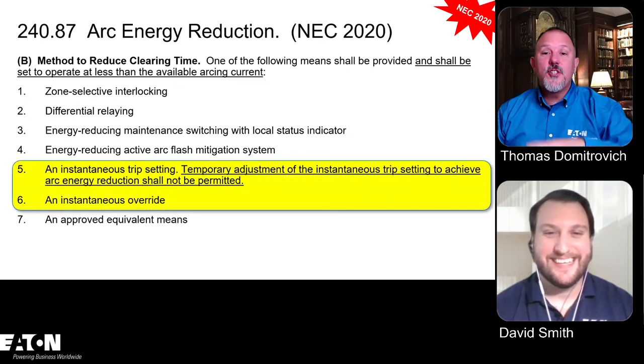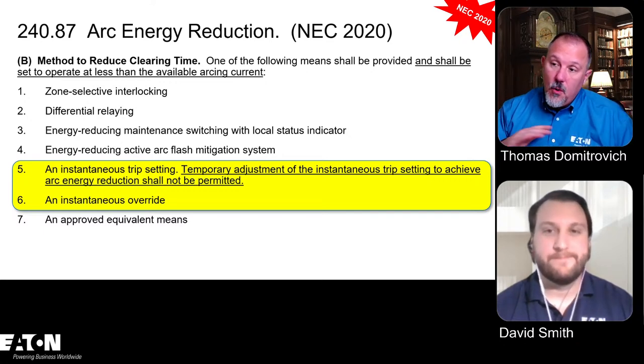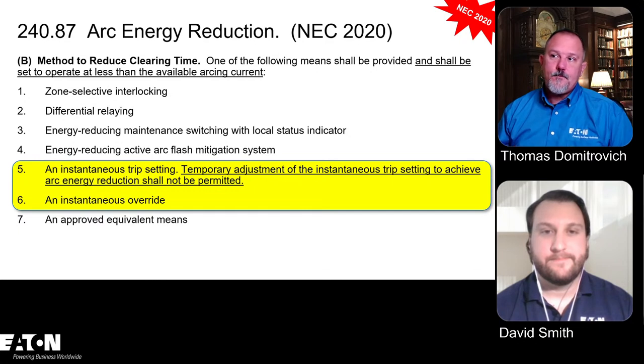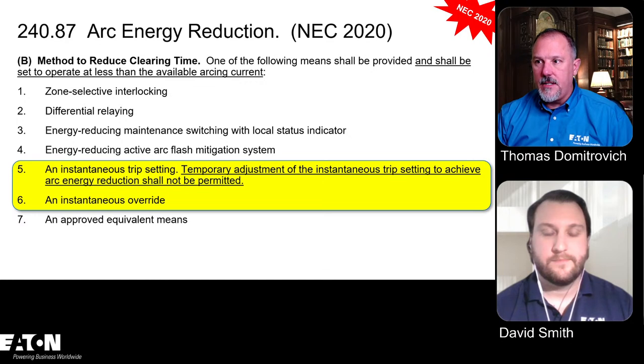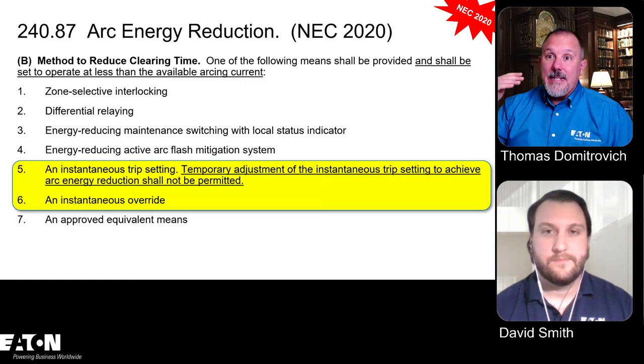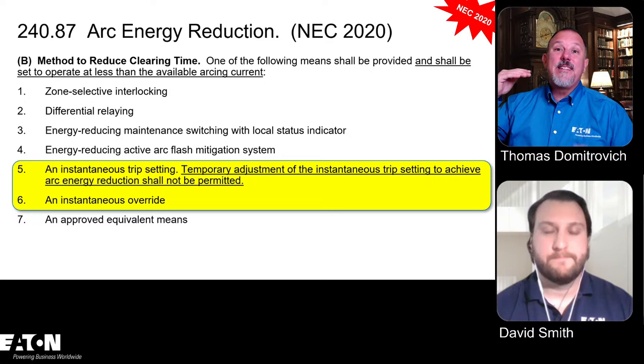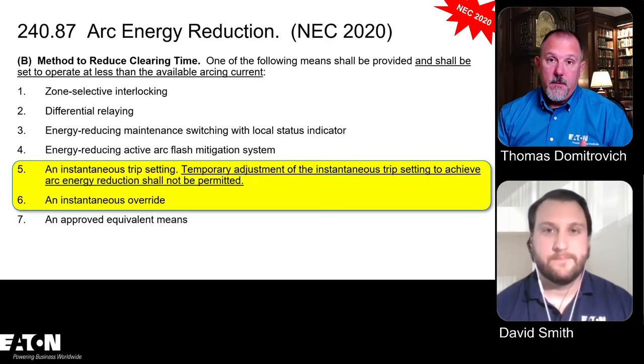So what we're going to do is we're going to start there because that's the most inexpensive solution in this whole bucket. And in reality, in many commercial applications, we're picking the overcurrent protective devices. We're picking standard molded case circuit breakers. We're series rating them. So I'm not worried about cascading events. I'm not worried about selective coordination. I'm not putting any intentional delays. The chances of me having an arcing current in that region are pretty good on some of these light commercial jobs.